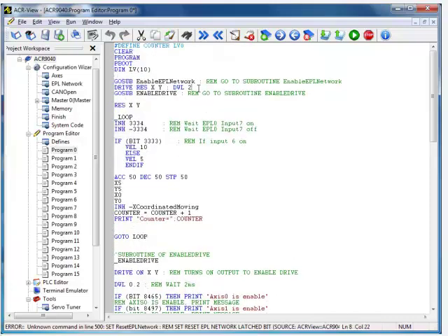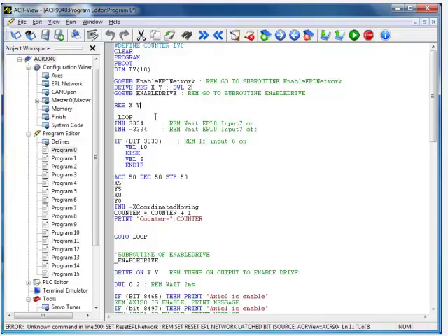If I do a reboot in the terminal emulator, it cycles power on the controller but not the drives. That will cause the drives to fault because they lose their EPL network. So you need to reset the drives to clear those faults before trying to enable the drives. So I've added a drive res XY, and then I do a 2 second delay before trying to enable the drives. Here's my reset on my X, Y.